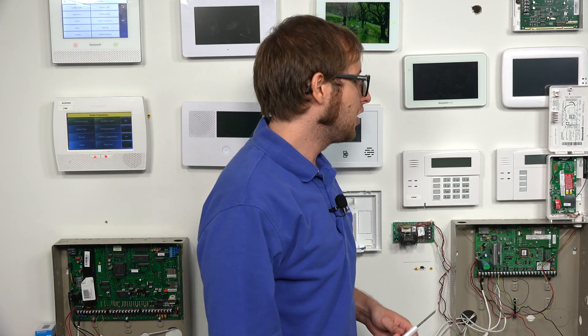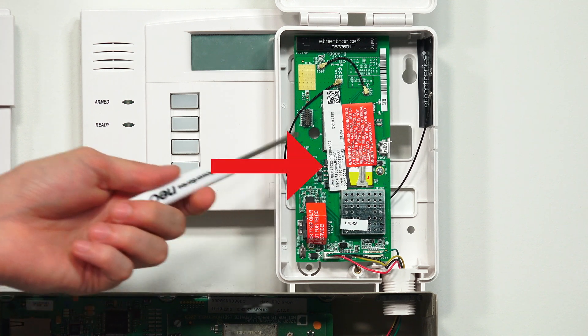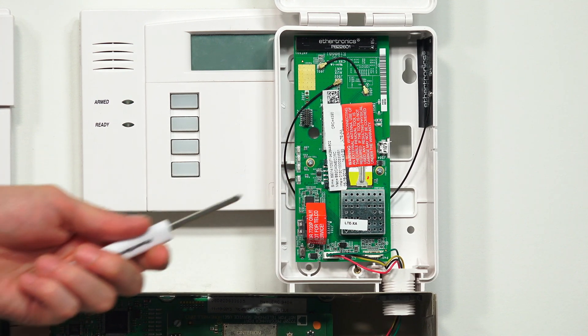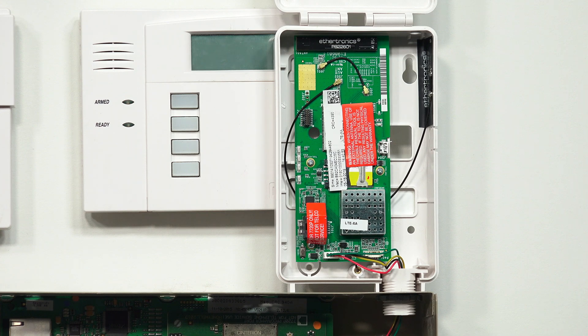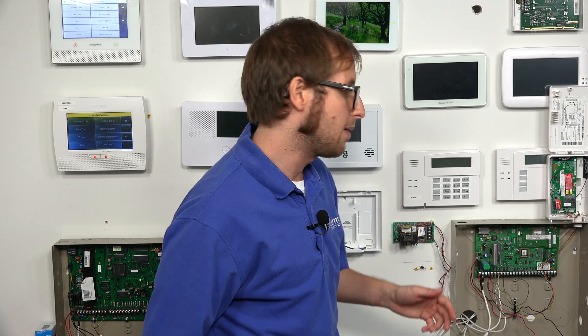One thing I do want to note before you go and close the module, make sure to write down the MAC and CRC codes on the communicator, on the sticker. Take a picture of them or write them down and keep them somewhere safe. You will need them for a monitoring service to activate the communicator. And I also want to note that this communicator will draw up to 250 milliamps of current when it's transmitting signals. So make sure to consider that into your current calculation and add an external power supply if necessary.